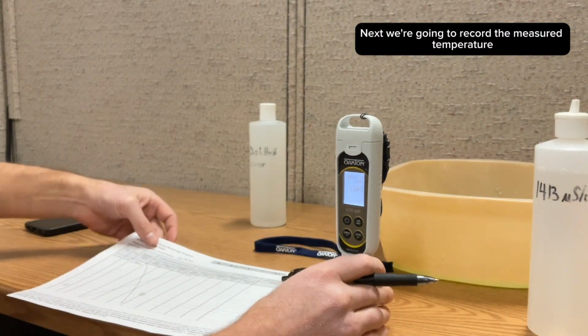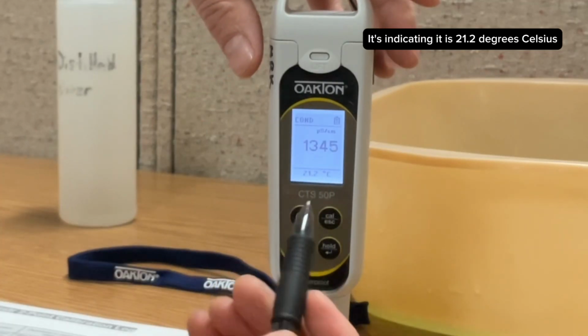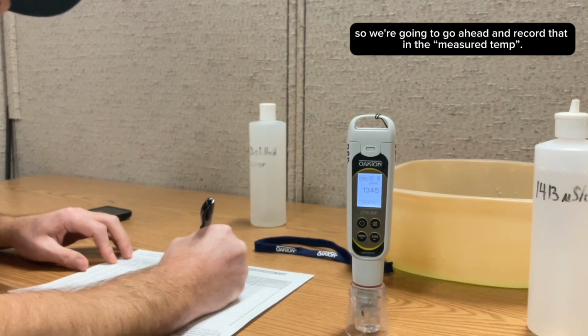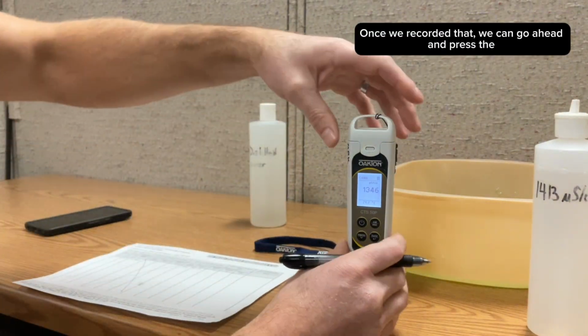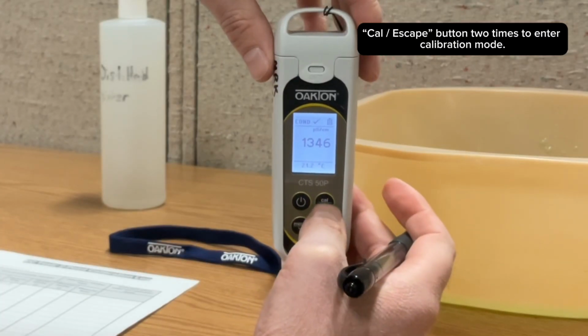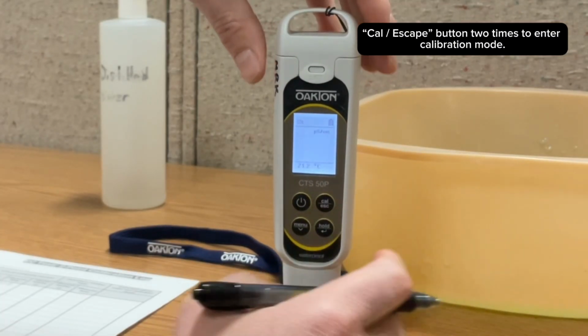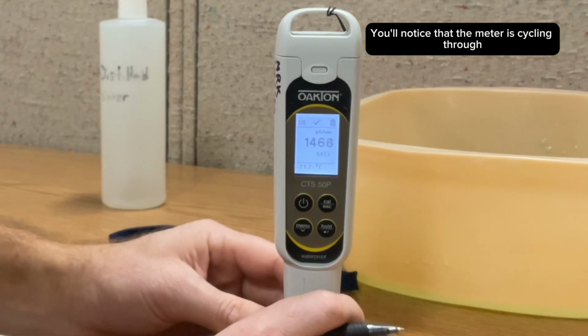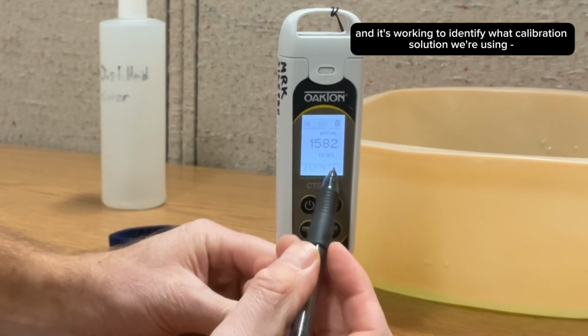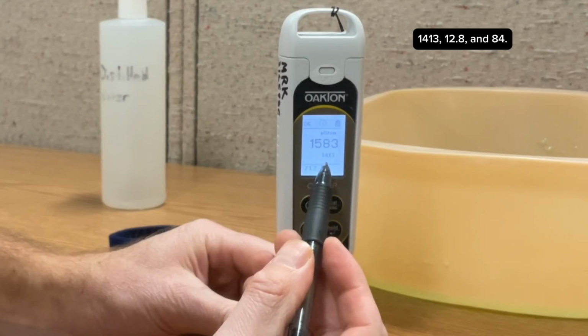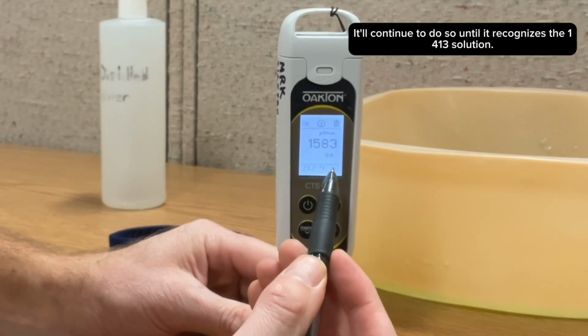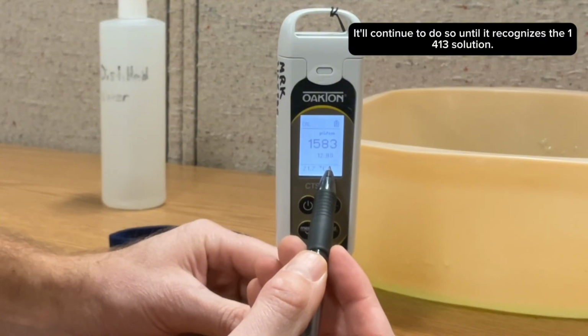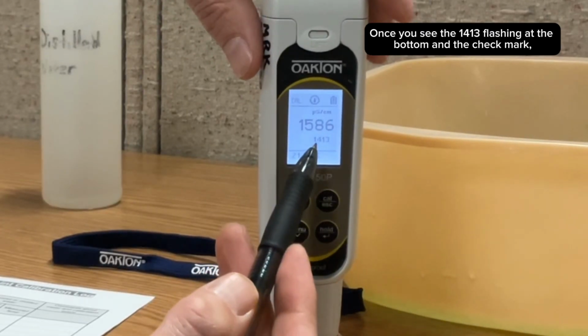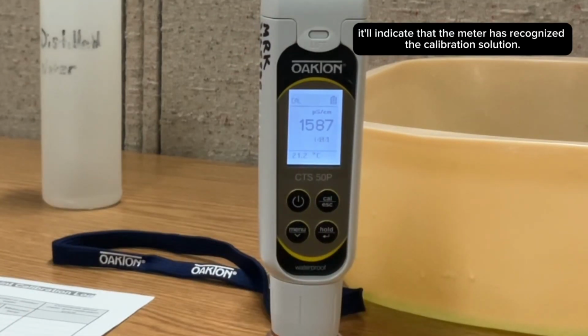Next, we're going to record the measured temperature, which is at the very bottom of your screen. It's indicating it is 21.2 degrees Celsius. So we're going to go ahead and record that in the measured temp. Once we've recorded that, we can go ahead and press the cal escape button 2 times to enter calibration mode. You'll notice that the meter is cycling through and it's working to identify what calibration solution we're using: 1413, 12.8, and 84. It'll continue to do so until it recognizes the 1413 solution. Once you see the 1413 flashing at the bottom and the check mark, it'll indicate that the meter has recognized the calibration solution.